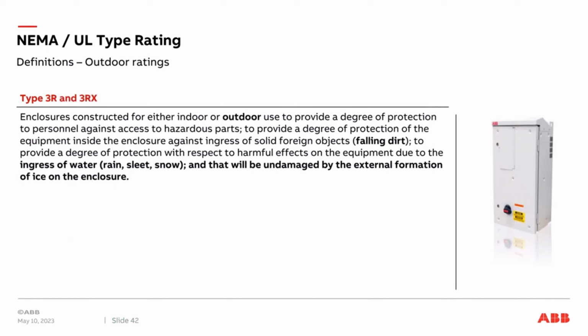A Type 3R and 3RX enclosure is designed for indoor or outdoor use. It gives you a degree of protection against personnel and falling dirt. It also protects you against the ingress of water, rain, sleet, or snow, and will be undamaged by external formation of ice on the enclosure. This does not mean you can wash it down with a garden hose. It's just for rain, sleet, or snow.